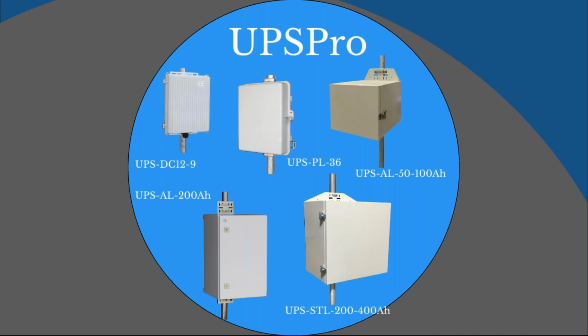Now, all of our UPS systems are solar ready. So if you have a site and you just want to give yourself some extra autonomy, you can add solar panels to any of these UPS systems. Again, you can see the 50 to 100 amp hour, the 200 amp hour, and 200 to 400 amp hour battery sizes that will fit in. When we design these, all of the components needed are included. With our RemotePro, you get our solar panels, battery bank, solar controller, enclosure for all the equipment, and all the cables and mounting hardware. You just need to provide the pole, unless it's the 720 watt array, and we provide that pole.